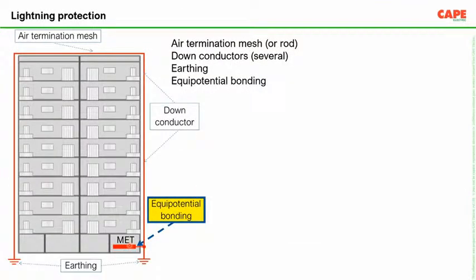Now, earthing: people always ask, do we earth lightning protection separately? No. One building shall have only one earthing. Say for example, in this particular building I have shown here, there is an air termination mesh at the top, then you have the down conductor, and at the bottom the down conductor is connected to MET. MET stands for the main earth terminal, nothing but the earth bus bar of that particular building. The earth bus bar of the whole building is MET.